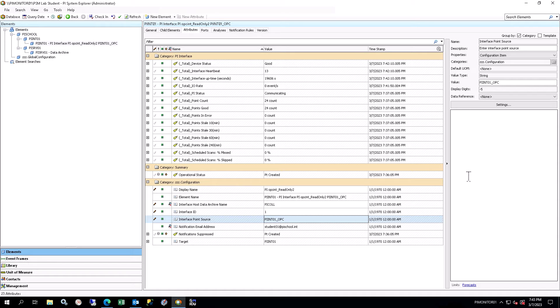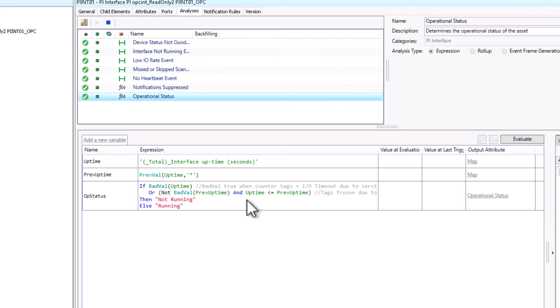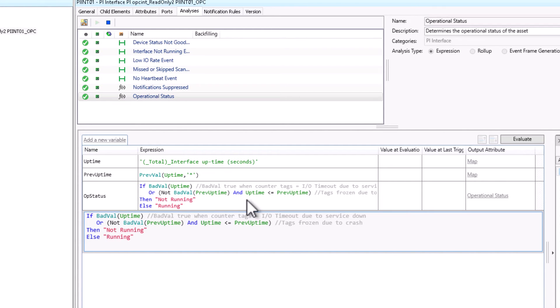Select the Attributes tab in the Viewer. Take a look at the Total Interface Uptime Seconds attribute. This is a PI Point data reference linked to a Windows Performance Counter that logs the total time that the interface has been running since it was last started. Go to the Analyses tab in the Viewer and select the Operational Status Expression Analysis. In the lower window, you will see three variables defined. The Uptime variable is getting the value for the Total Interface Uptime in Seconds attribute. The variable PreviousUptime is getting the previous PI Tag value for the same attribute. The variable OpStatus uses the above two variables to see if the service has stopped or crashed and sets the Operational Status Analysis Output attribute value accordingly.